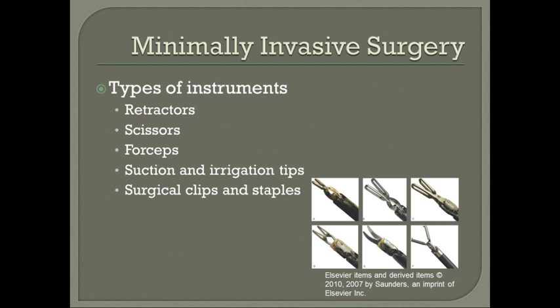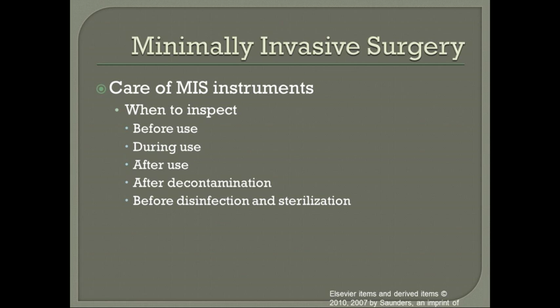Minimally invasive instruments are similar to those used in open surgery. There are retractors, scissors, forceps, bipolars, and bovies. The chain of care starts before surgery and continues through the intraoperative and postoperative reprocessing periods. Electrosurgical instruments must be checked for breaks in insulation. Even a small defect may result in an unintentional burn. All instruments must pass through a cleaning and terminal decontamination or sterilization process immediately after use.